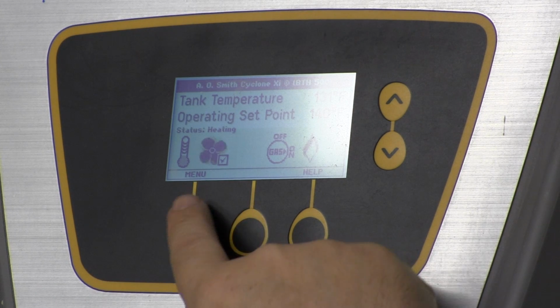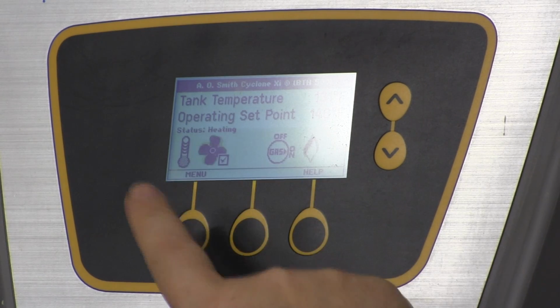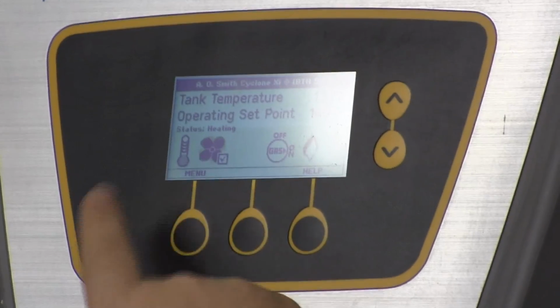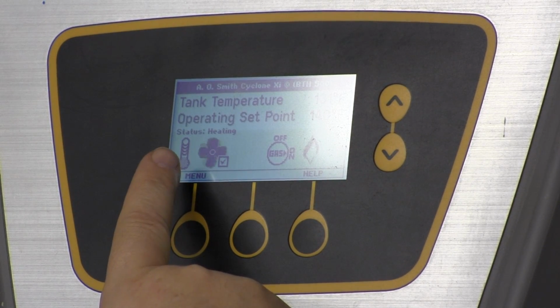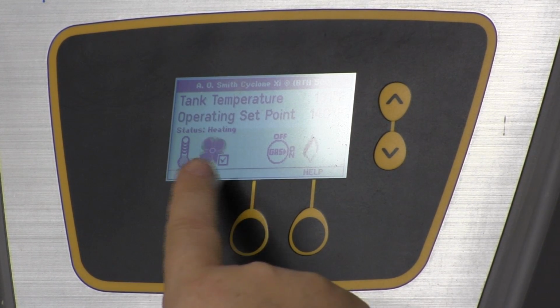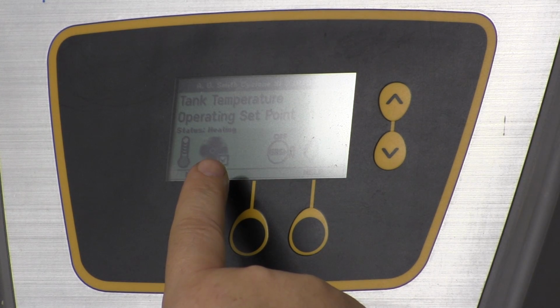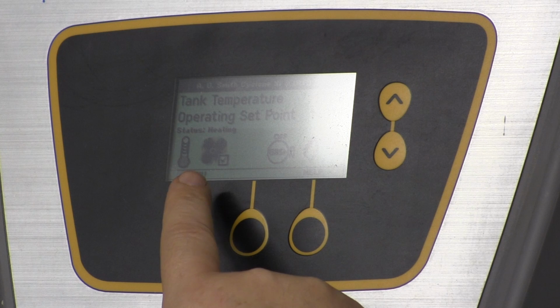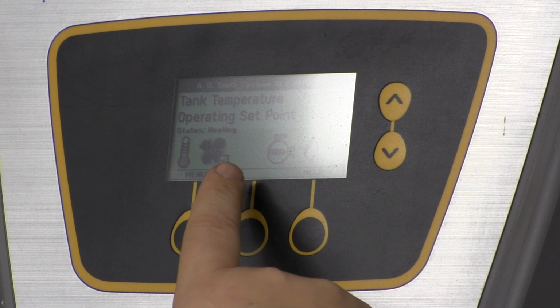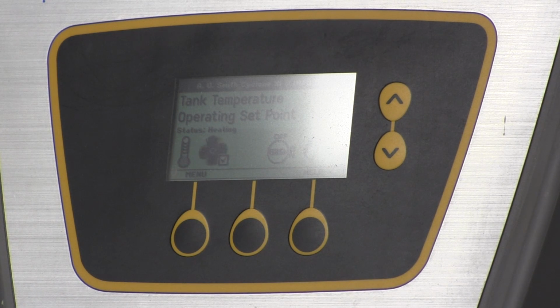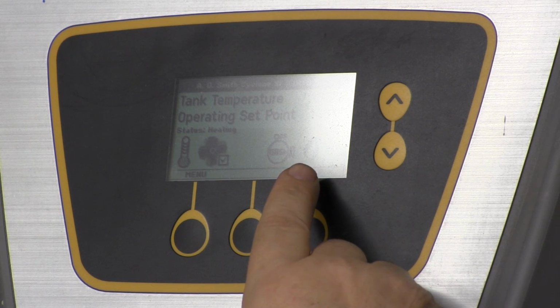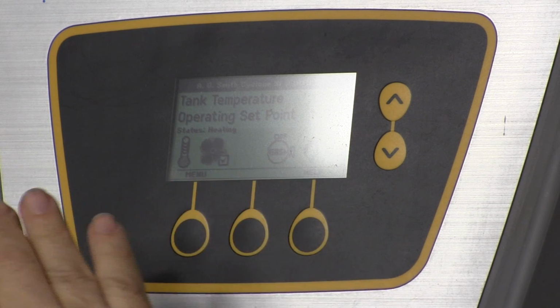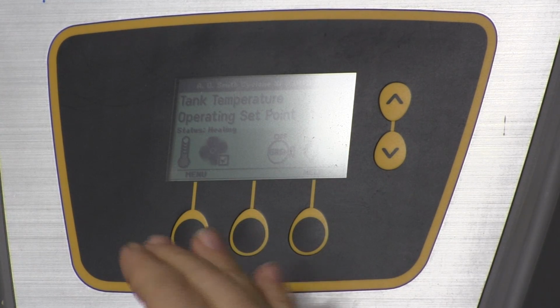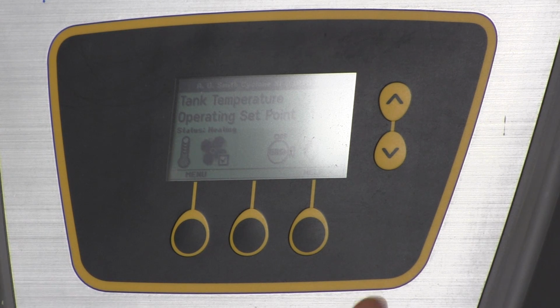When the heater fires, there is a visualization of the sequence of operation. The little thermometer says, I'm calling for heat. I'm cold, I want heat. The fan will go on, the blower will go on for 30 seconds and purge any gas or air that might have been left over from before. Then the little igniter comes on, which is a little glow stick in there, and once that's proved that it's hot and ready to go, it'll open up the gas valve and the heater will fire and you'll see this little flame. So everything that's happening within the unit, you can visually see right there on the unit. And I've sat and watched that movie many times.